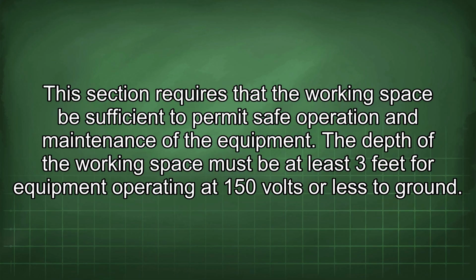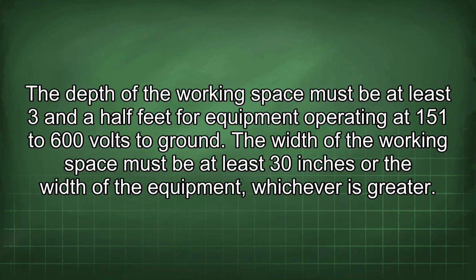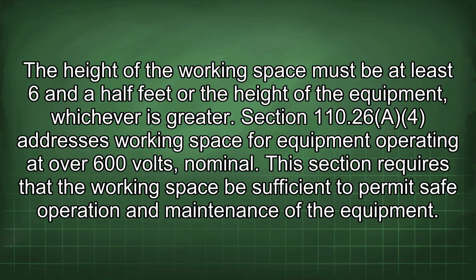The depth of the working space must be at least 3 feet for equipment operating at 150 volts or less to ground. The depth of the working space must be at least 3.5 feet for equipment operating at 151 to 600 volts to ground. The width of the working space must be at least 30 inches or the width of the equipment, whichever is greater. The height of the working space must be at least 6.5 feet or the height of the equipment, whichever is greater.